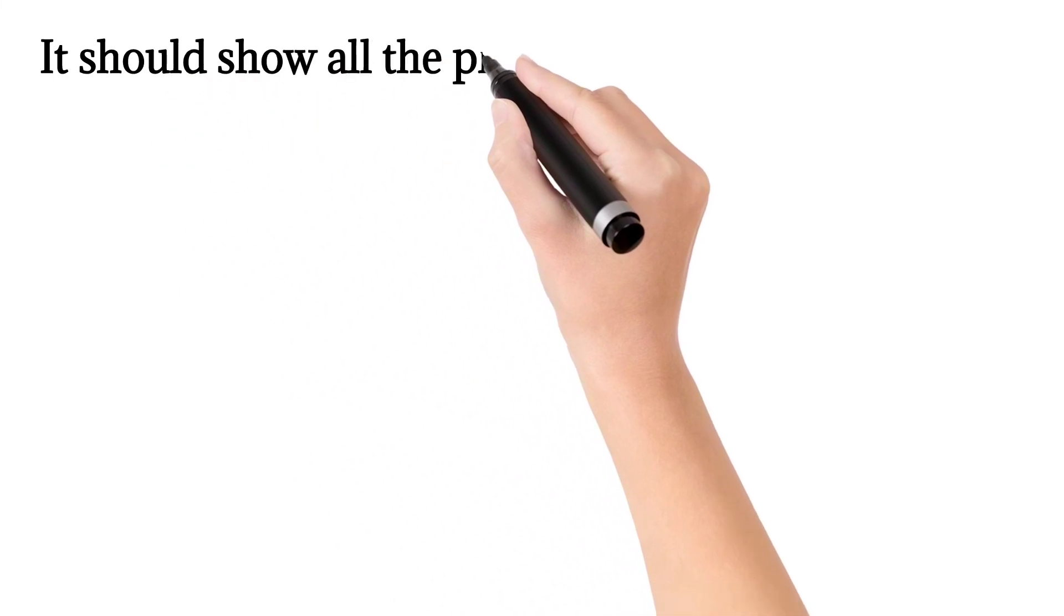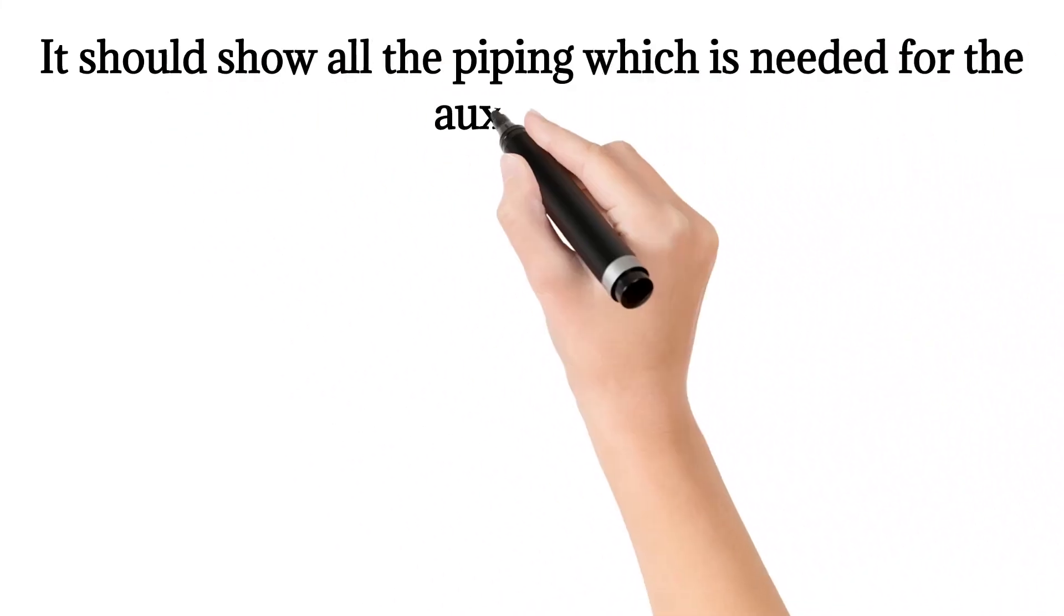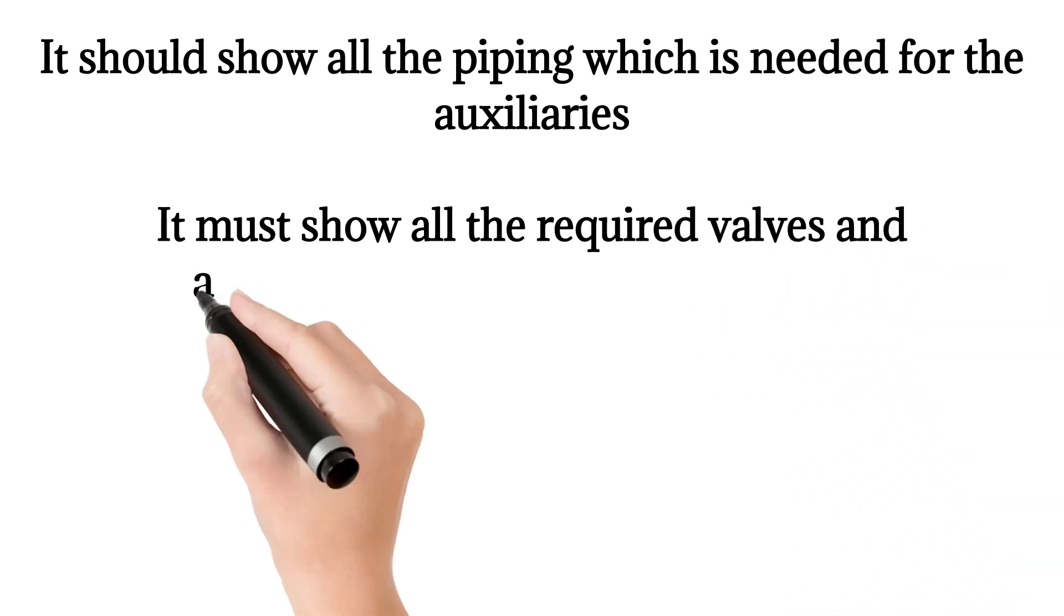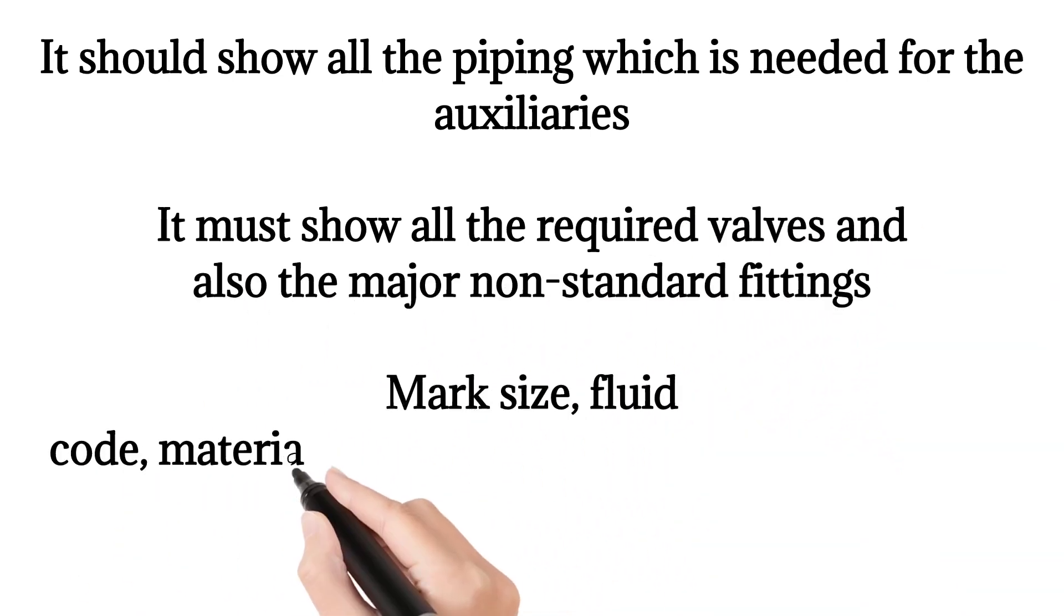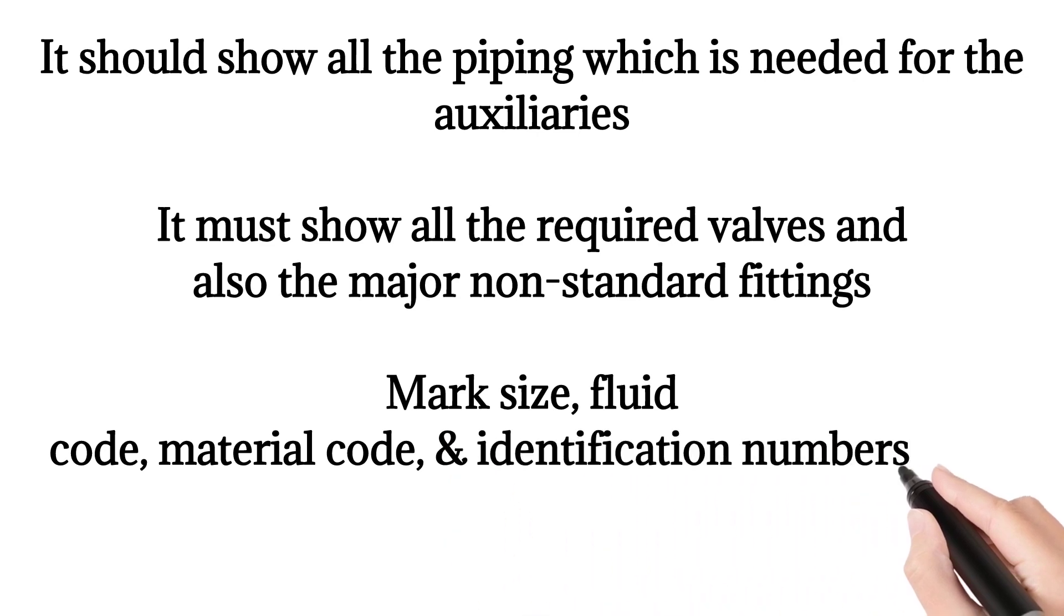It should show all the piping which is needed for the auxiliaries. It must show all the required valves and also the major non-standard fittings. Mark size, fluid code, material code, and identification numbers of all the pipelines should be included.